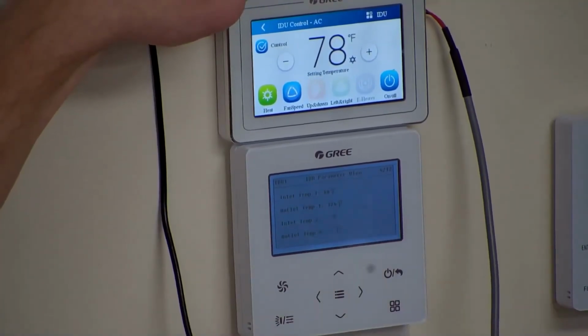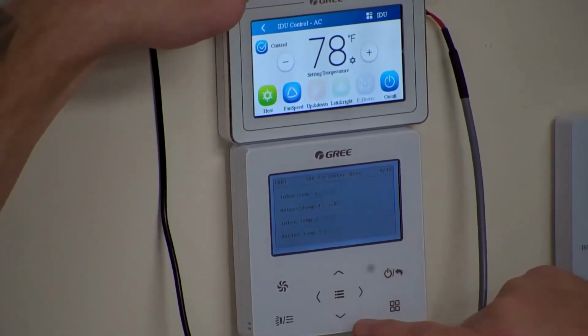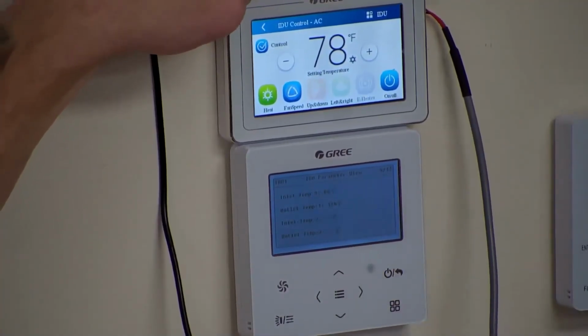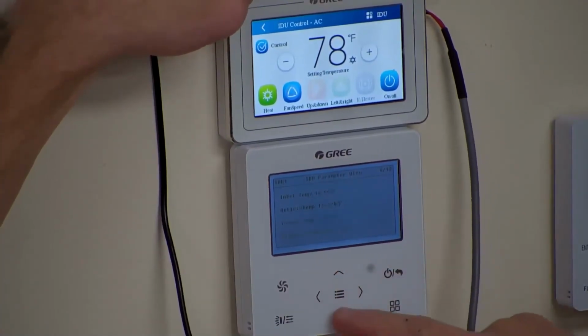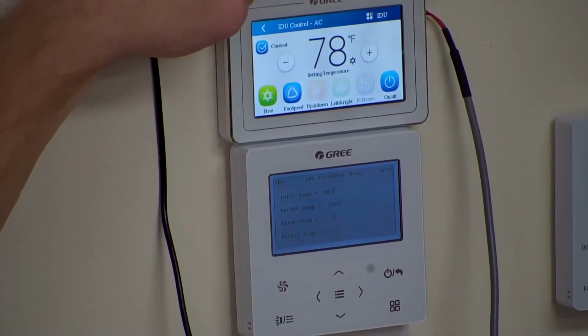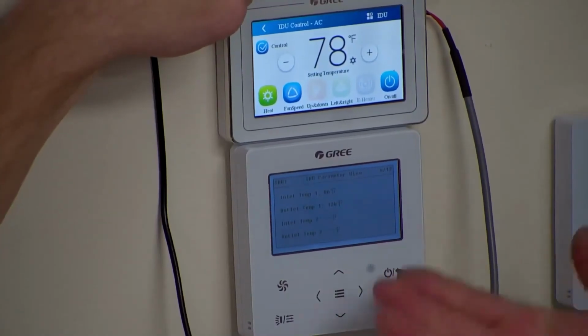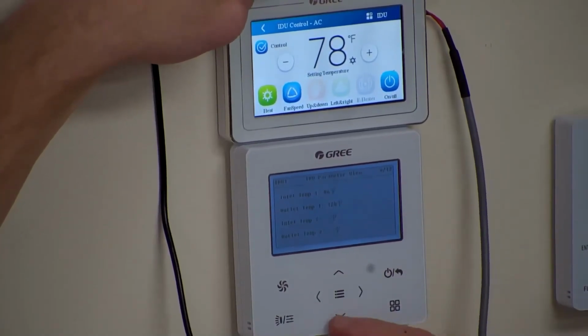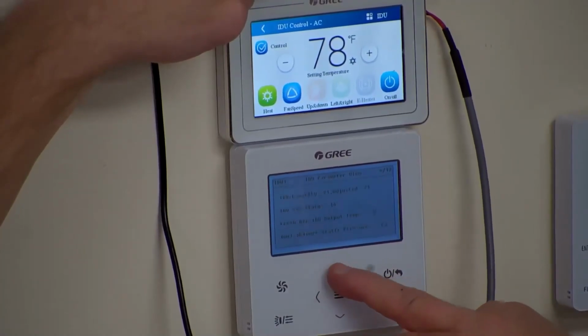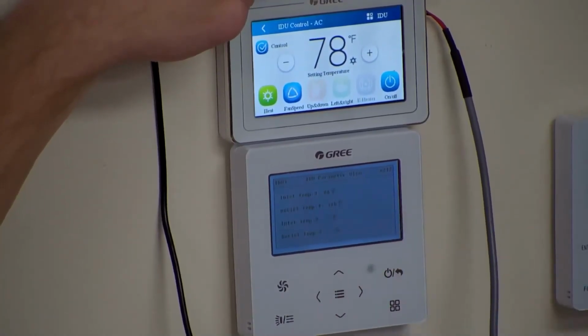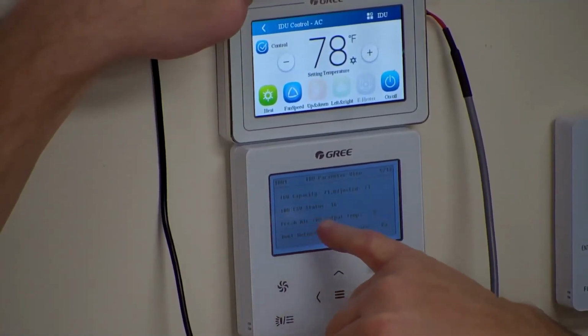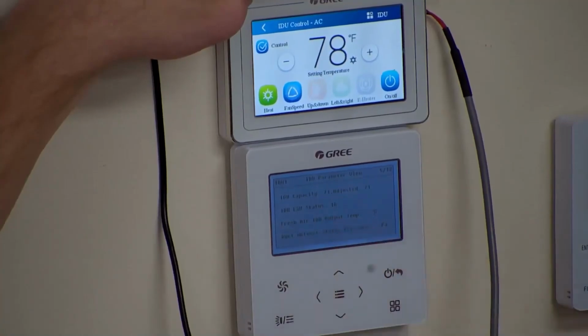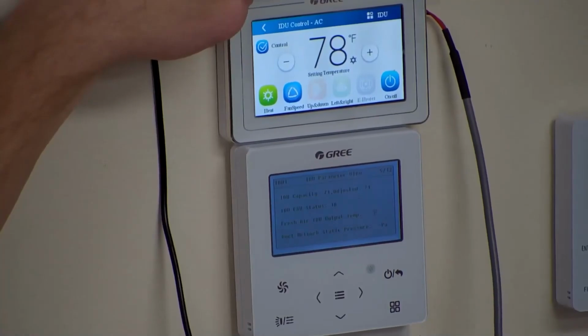Inlet, outlet temperatures. So if you've got a wired controller, you can actually go see this information on the wired controller as well. But if you've got all cassettes and all wall mounts and you don't add the optional wired controller, now you have no diagnostic information because you can't do this with the remote. This gives you some really good information. And it'll also go through here and it will give me the EEV step. Indoor unit EXV status, 16. So that one's a little trickier too, so let me point that out.